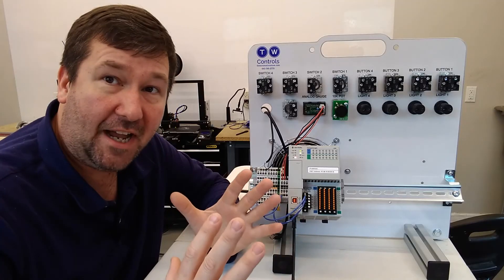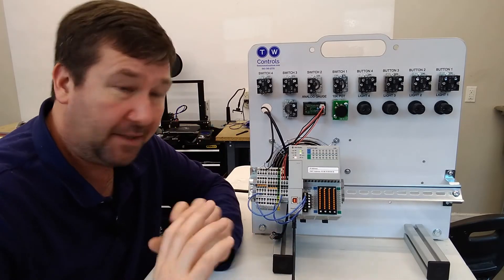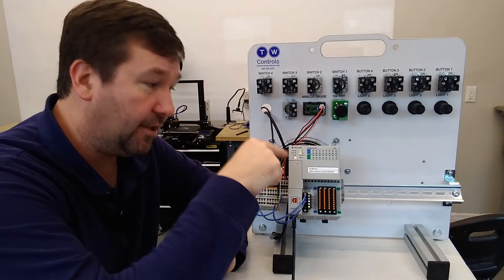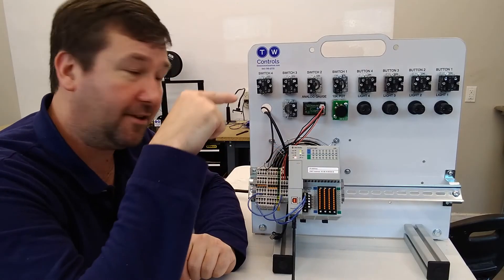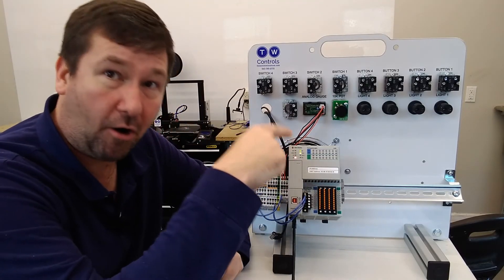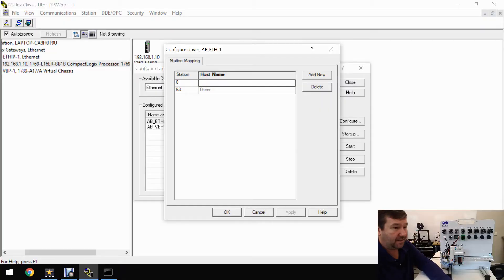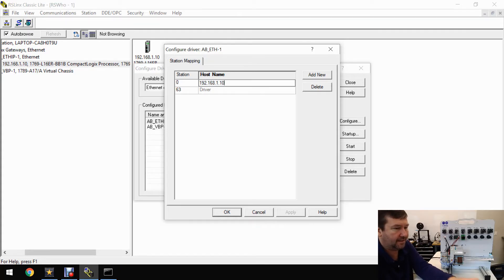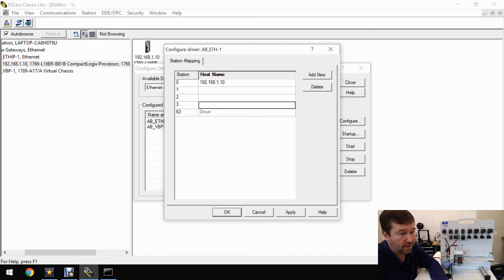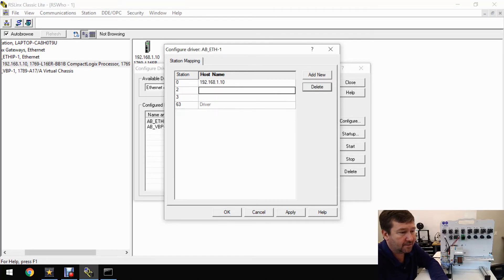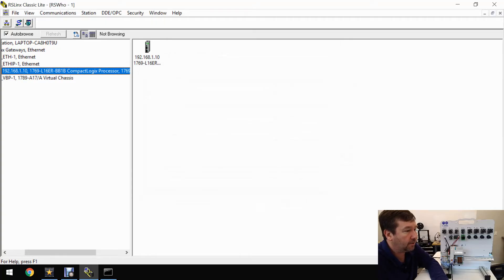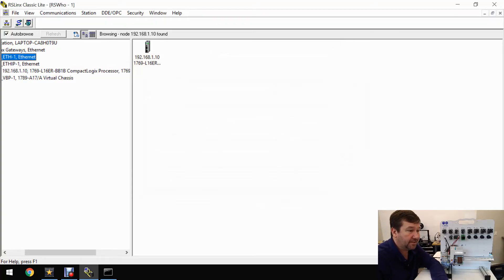This time, it's going to ask us, where do I need to go look for PLC? The Ethernet IP driver, the devices kind of shout out 'hey, here I am.' But the devices driver, the PC is going to go and look and say, okay, 192.168.1.10, are you really there? So we're going to type in a station of 192.168.1.10. If you had more, you could click the add new button and add additional ones, .11, .12, however many you need to do this way. Click OK, close. Then we're going to go to this Ethernet driver, and there's our PLC again.